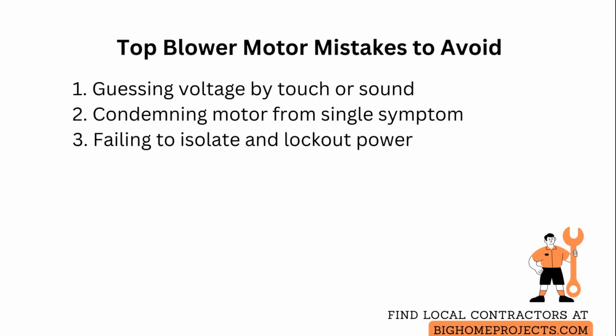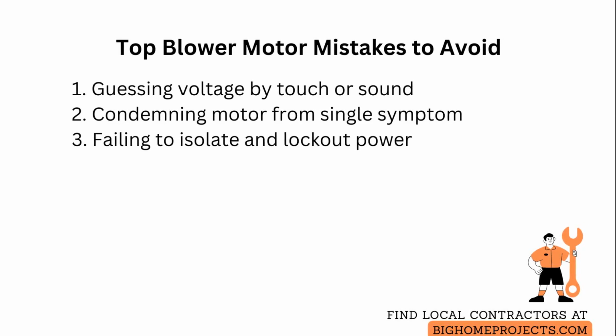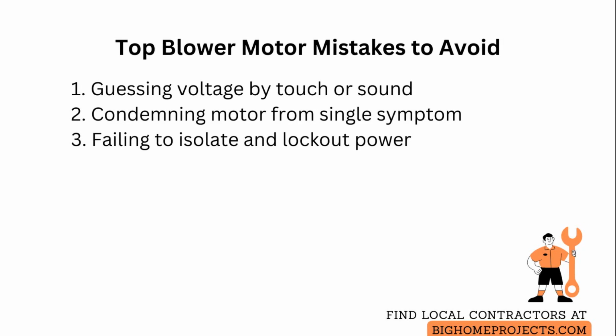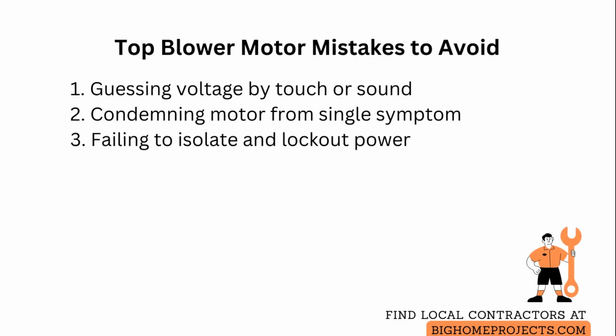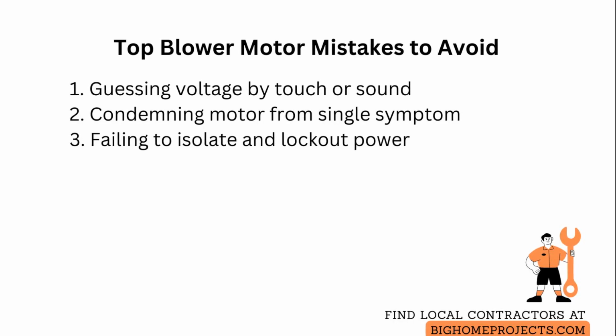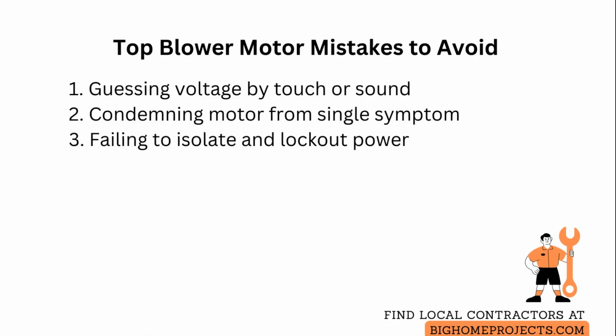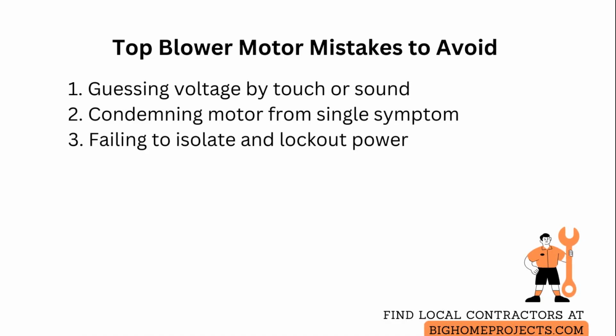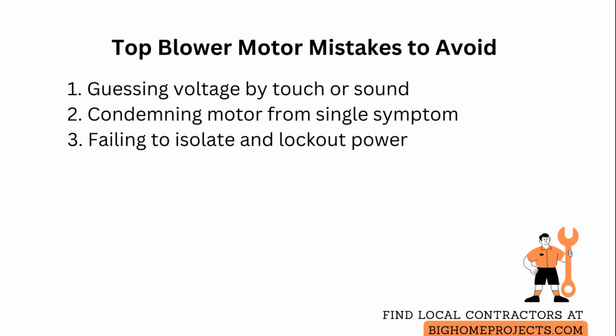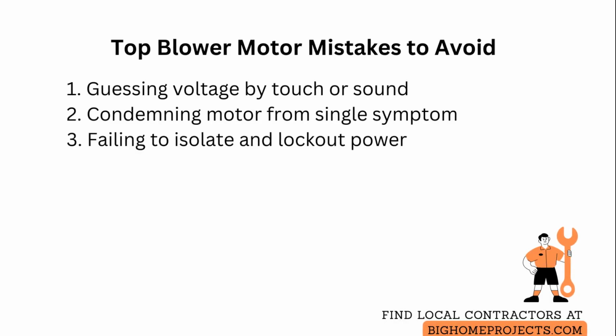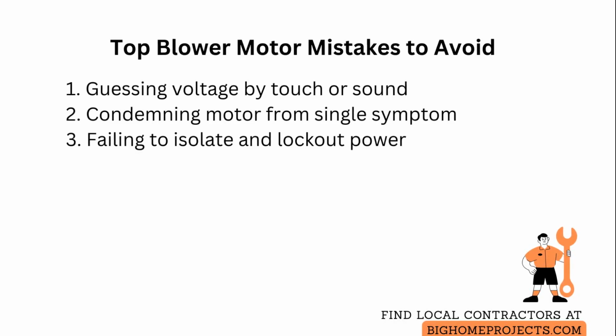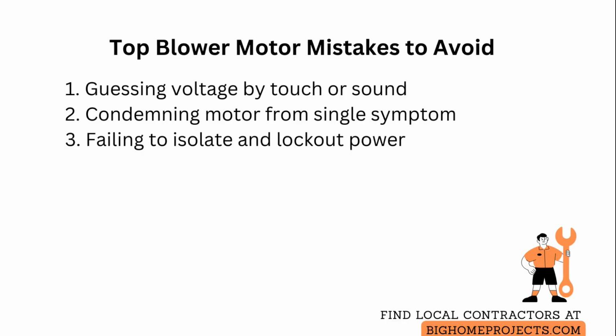Relying on a single symptom such as noise to condemn the motor can lead to unnecessary replacement. So pair auditory clues with measured current draw and a capacitor check. Failing to isolate and lock out the power when switching testing modes risks short circuits and arc flash. So implement lockout, tagout, and verify zero voltage with your meter before contacting the system.